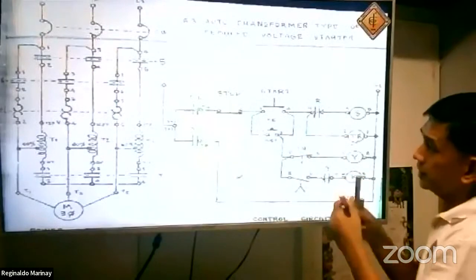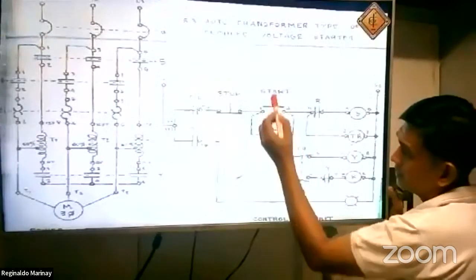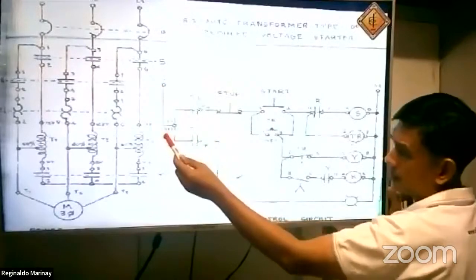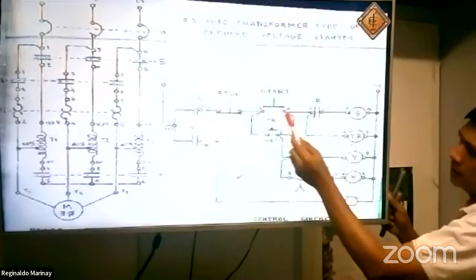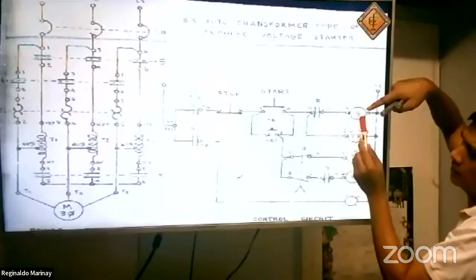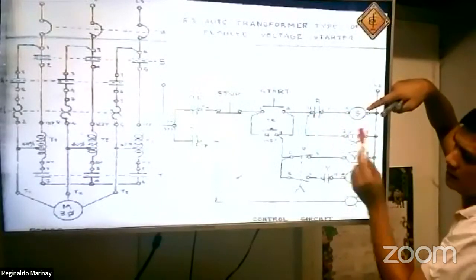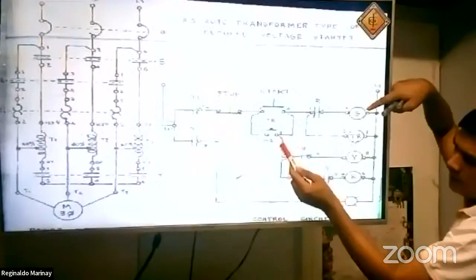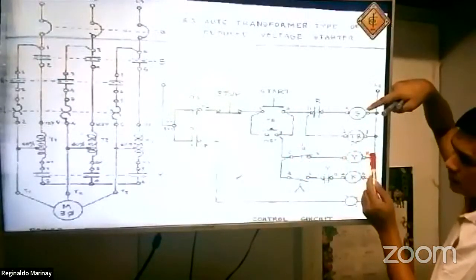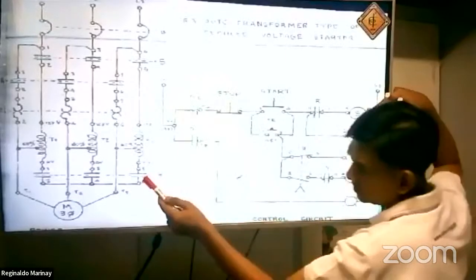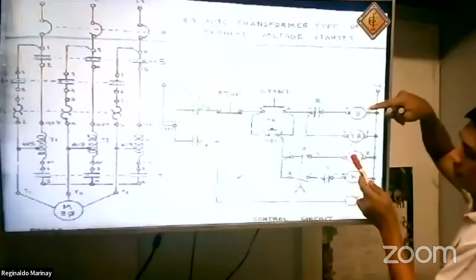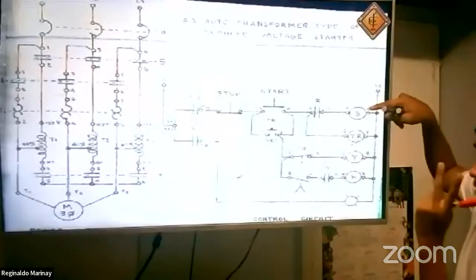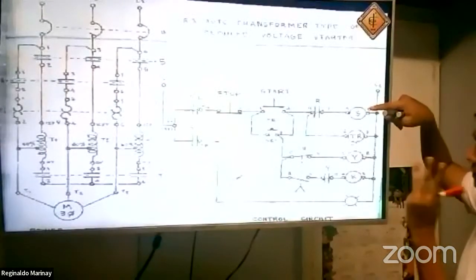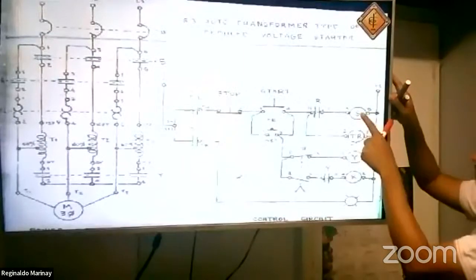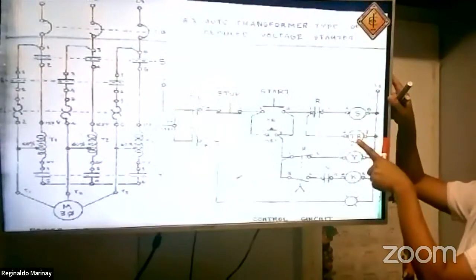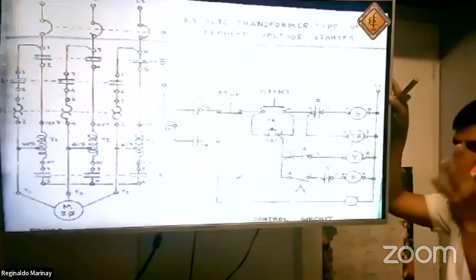Let us press the start push button. The current will flow here. Take a look here, energizing your S contactor. Also energizing your timing relay. Also, take a look, this becomes energized. Also your Y contactor, this contactor. Okay, so there are 3 holding coils being energized. The 2 magnetic contactor coils and the timing relay coil become energized initially.